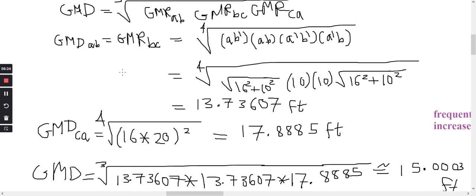Next, let's calculate the overall GMD. Using the rule, it's the cubic root of 13.73607 times itself times 17.8885, which is 17.8885 times 13.73607 squared. That comes out to approximately 15.0003 feet. That's the GMD, now calculated.